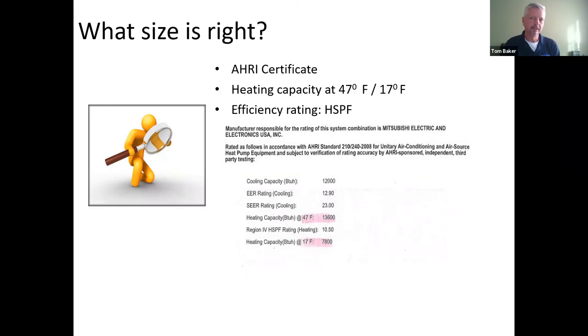That's critical. If we oversize it, and we have to fight with people who think bigger is better all the time. If we say they need a 3-ton heat pump, they want a 4-ton heat pump, right? But oversizing is the worst mistake you can make with heat pumps. An oversized heat pump won't last. It'll cycle on and off way too frequently and wear itself out. It doesn't dehumidify properly in the summertime, and it can overheat easily in the wintertime.